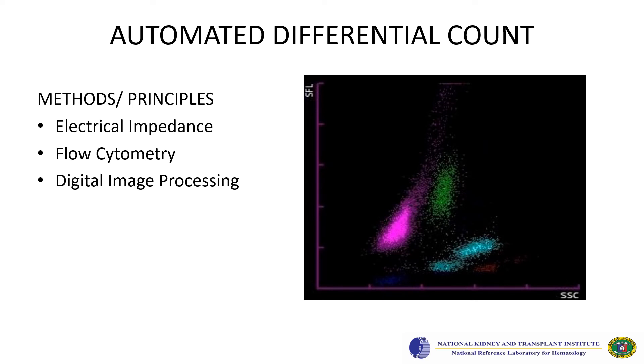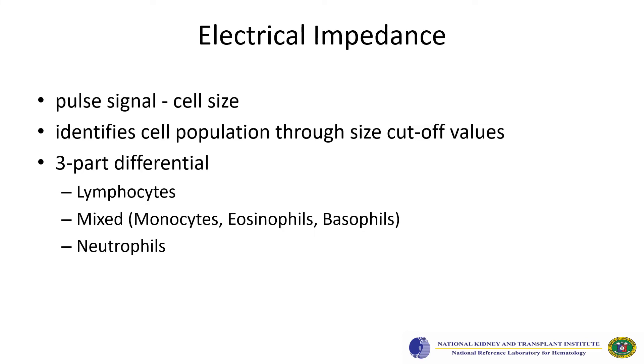Clinical laboratories use different methods and principles in automated differential counting: electrical impedance, flow cytometry, and digital image processing. In the use of electrical impedance for the WBC differential count, the pulse signal determines the cell size, and the algorithm identifies cell populations through size cutoff values. With this, it is able to generate a three-part differential, which includes lymphocytes, a mixed cell population, and neutrophils.